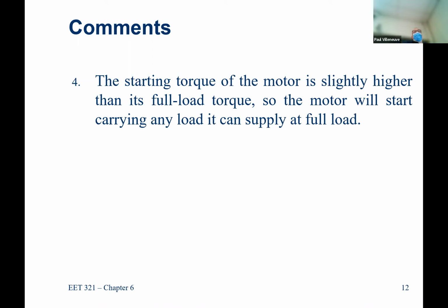And then as it gets more and more speed, it has to do more and more. So pumps usually can start pretty easy. Fans are a real struggle. And keep in mind, these aren't the box fans that you're going to buy at Walmart for $17, right? If this is a big motor, it's not unlikely to have a 2 foot, 3 foot diameter, and it's not going to be made out of plastic. They're going to be made out of metal, right? Some sort of a steel.